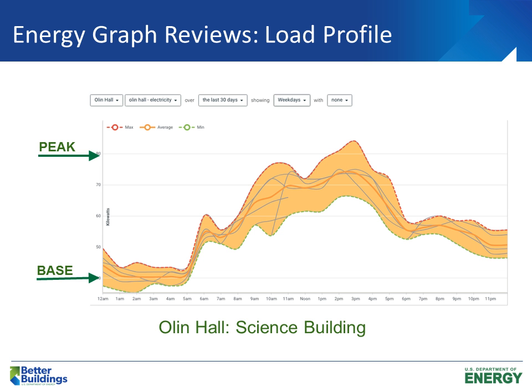We do look at the load profile, which you saw earlier, and we're looking both at our base and our peak, the difference between them, the ratio, and also the actual value, because this is helping us get familiar with which buildings are sort of residing in which zones. And we not only look at the difference between peak and base. If there's a big difference between peak and base, we possibly have some room in our occupancy and what's happening when the building's occupied. But we also look at that base load and try to see if our equipment operation could be reduced at all during those unoccupied times.